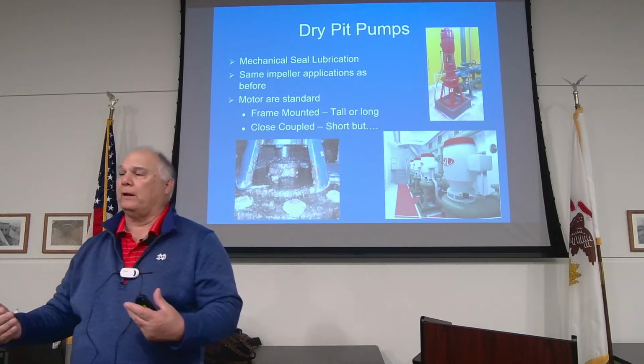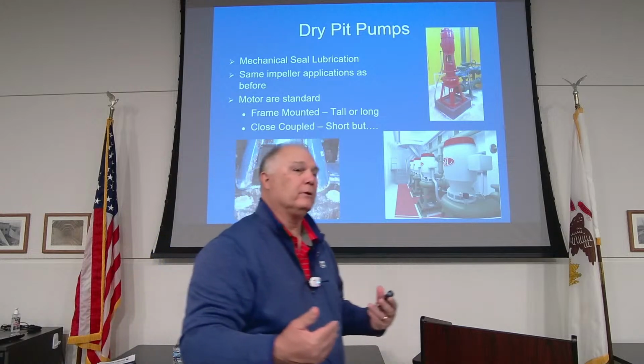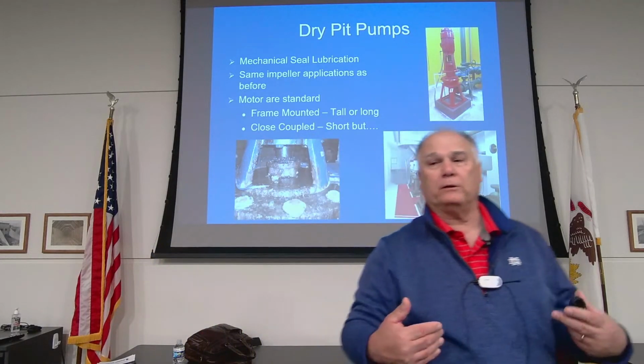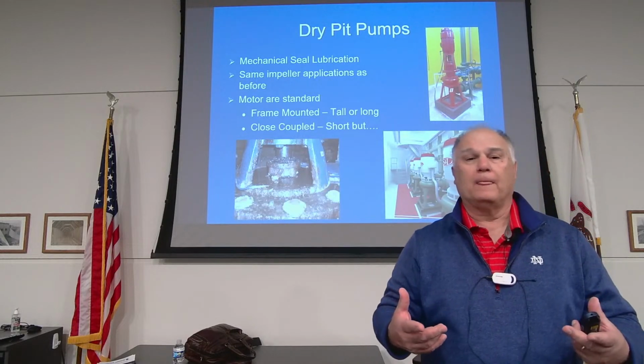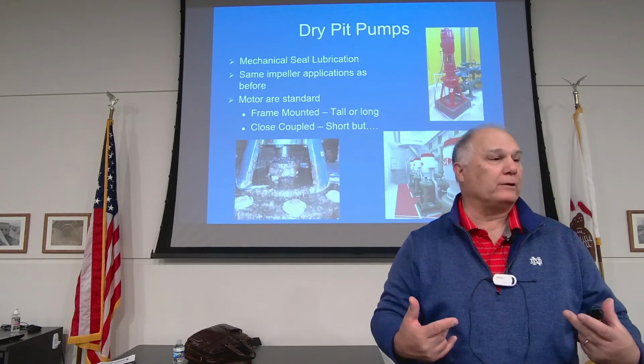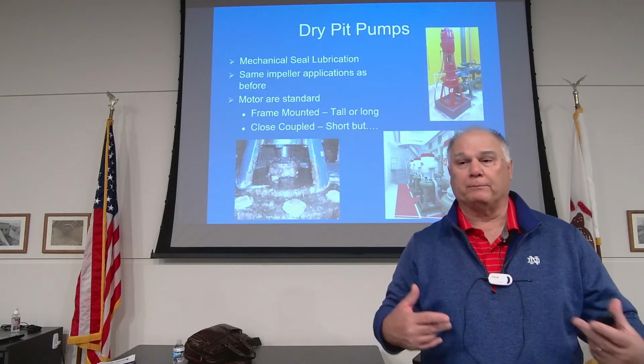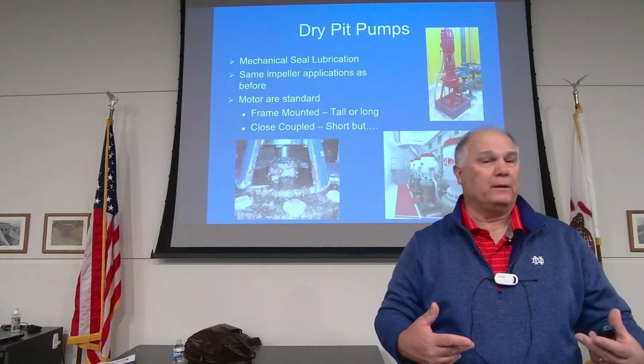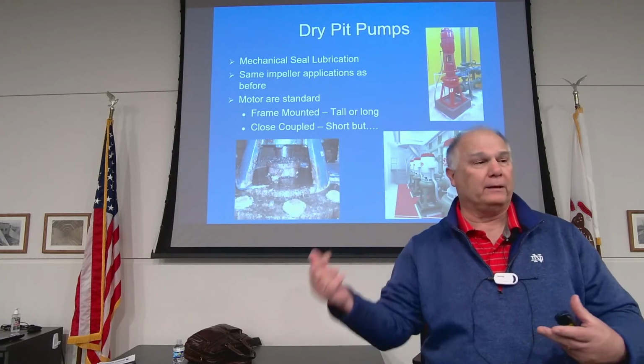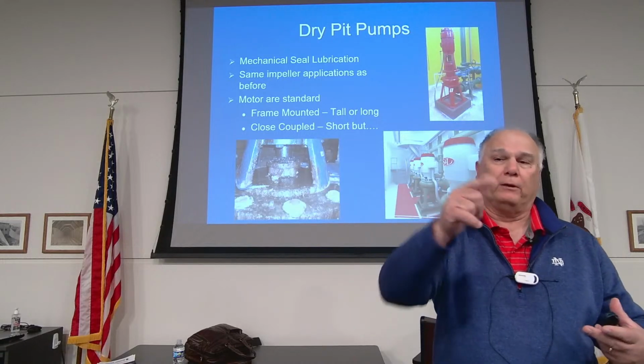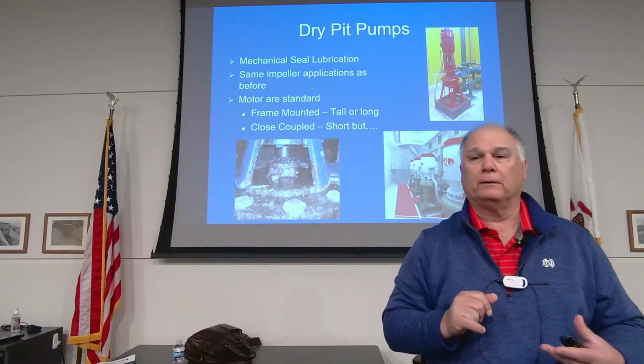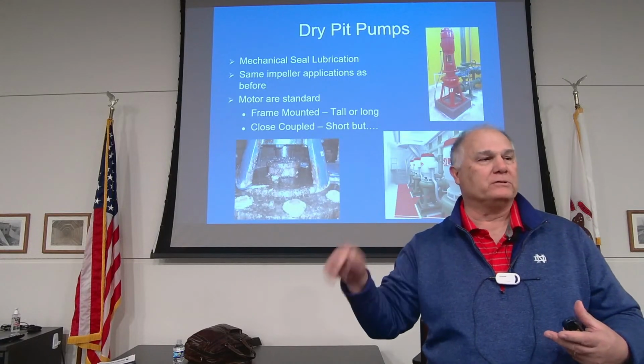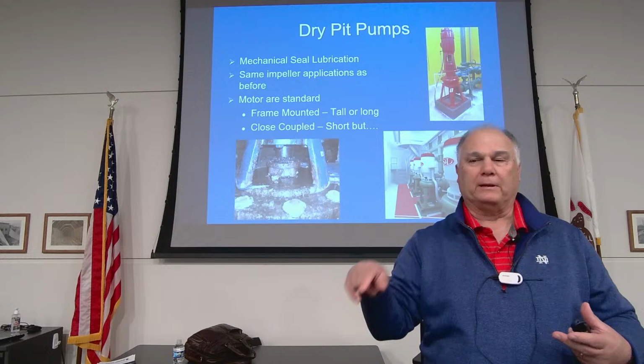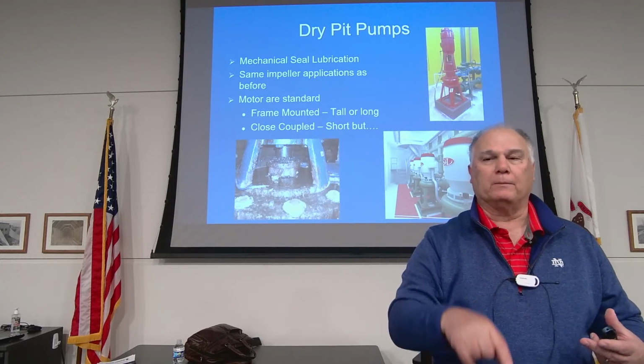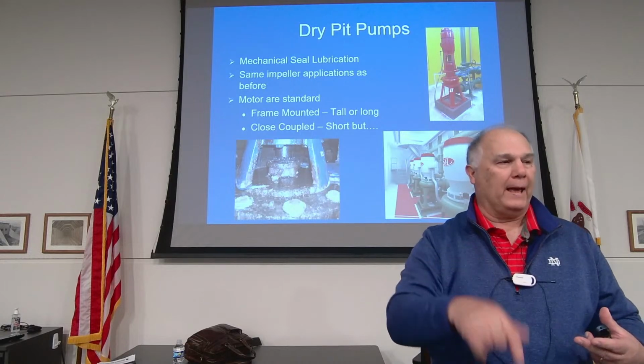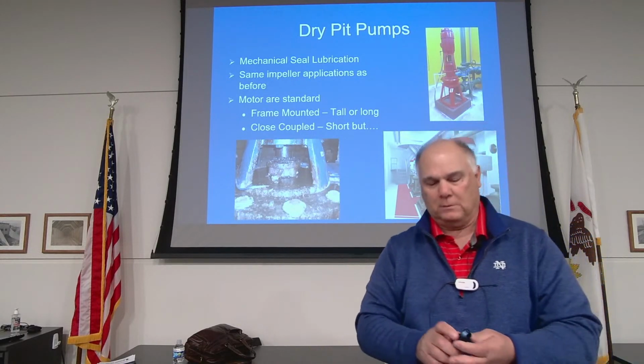So it's important to understand that when the engineering firms design pump stations, they need to say, all right, we know we're going to do a 6-inch pipe, but we only have 100 gallons a minute that we're actually going to pump now. But we still have to design the pump station to pump that 300 gallons a minute going up, because we've got to get that water up and over through the check valve to get into the force main. So even though they might say they're only going to pump this now, they need to pump the volume the station's designed for, not what their flow is now. That's an important thing to understand.